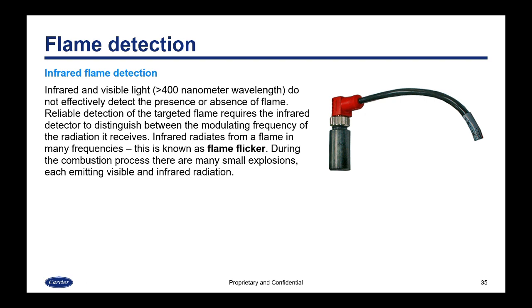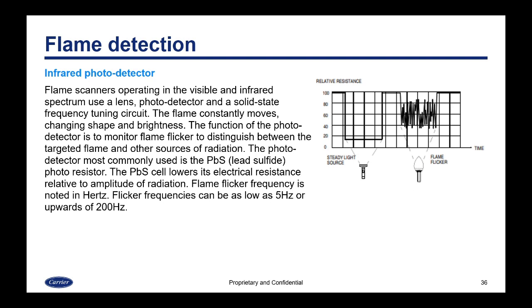Infrared and visible light — greater than 400 nanometer wavelength — do not effectively detect the presence or absence of flame by themselves. Reliable detection requires that the infrared detector distinguishes between the modulating frequency of the radiation it receives. Infrared radiation from a flame is in many frequencies — this is known as flame flicker. During the combustion process there are many small explosions, each emitting visible and infrared radiation. Flame scanners operating in the visible and infrared spectrum use a lens, photo detector, and a solid state frequency tuning circuit. The photo detector most commonly used is the PbS or lead sulfide photoresistor. The PbS cell lowers its electrical resistance relative to the amplitude of radiation. Flame flicker frequency is noted in hertz and can be as low as 5 Hz or upwards of 200 Hz.